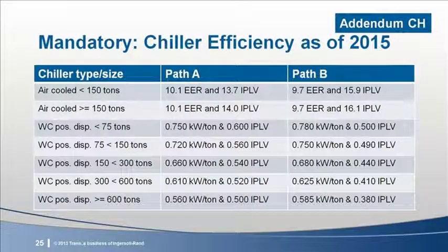90.1 2013 saw the first significant upgrade to the chiller efficiency requirements since 1999. Each chiller type, other than absorption, has 2 paths to compliance, each with a full load and a part load metric to meet. Here you see the air-cooled and positive displacement water-cooled requirements, and positive displacement would include compressor styles such as reciprocating, screw, and scroll types. The improvements in these categories include a new Path B for air-cooled chillers and a new category for water-cooled positive displacement chillers at or larger than 600 tons, with efficiency requirements for both paths that match the centrifugal requirements at or greater than 400 tons.